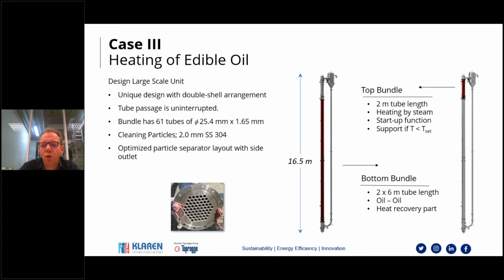So this is an oil section with a lot of emphasis on improving the shell side heat transfer by proper design. In total, this bottom bundle is 12 meters in height. And this bottom bundle is then followed by a top bundle, 2 meters in height, which is driven by steam. Why did we have this top bundle in addition?